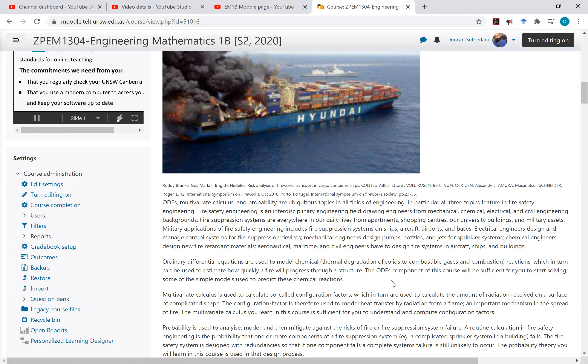Probability theory and probability distributions are used to model the risk from fire or the risk of a fire suppression system failing. A routine task in fire safety calculations is to draw up a circuit diagram of the sprinkler system — all the pumps, sprinkler heads, and detectors — assign probabilities of failure to each component, and estimate the overall probability that the fire suppression system fails completely. You want that probability to be very small, so you design the system with redundancies, and you'll get the basic probability tools needed to do that in this course.